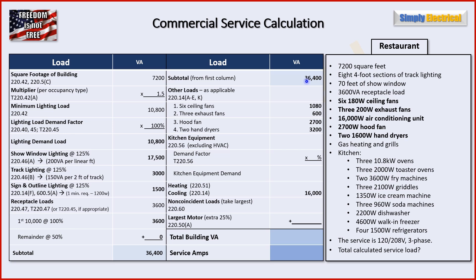We slide that subtotal over to the next column and take our other loads. We have six 180-watt ceiling fans — 1,080 VA; three 200-watt exhaust fans — 600 VA; a 16,000-watt air conditioning unit, which we'll drop down under cooling for the non-coincident load comparison; a 2,700-watt hood fan; and two 1,600-watt hand dryers — 3,200 VA. The hood fan is in the kitchen, but per 220.56, any HVAC — heating, ventilation, or air conditioning — is excluded from kitchen equipment and goes here under other loads.